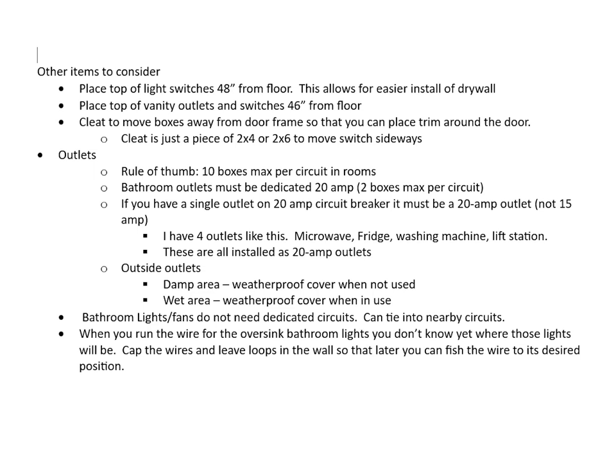Outlets. Rule of thumb, 10 boxes max per circuit in rooms. Bathroom outlets must be dedicated 20 amp, 2 boxes max per circuit. If you have a single outlet on a 20 amp circuit breaker, it must be a 20 amp outlet, not a 15 amp outlet. I have 4 outlets like this: microwave, fridge, washing machine, and lift station. These are all installed as 20 amp outlets. Outside outlets. Damp area. Weatherproof cover when not used. Wet area. Weatherproof cover when in use. Bathroom lights and fans do not need dedicated circuits. They can tie into nearby circuits.